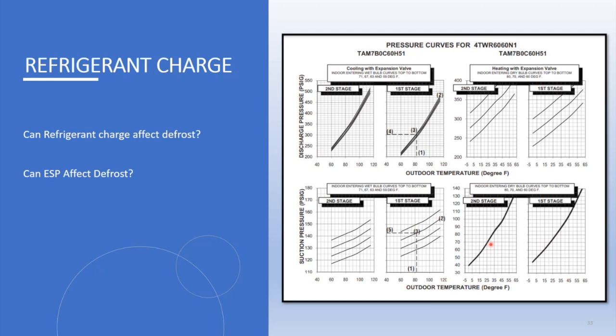If you're off, I wouldn't immediately jump to adding or removing refrigerant or doing a reweigh. I would take a look and go, okay, I'm high on my pressures, so maybe take a look at the indoor side, because if your pressures are high in heating mode, that's going to be an indoor issue probably. So I'd be looking at the indoor filter, dirty indoor coil, indoor airflow, things like that.